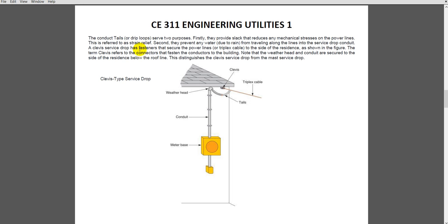As for the clevis, the drip loops serve two purposes. Firstly, they provide slack that reduces any mechanical stress on the power lines. This is referred to as strain relief. Second, they prevent any water due to rain from traveling along the lines into the service drop conduit. A clevis service drop has fasteners that secure the power lines or triplex cable. So our weatherhead is attached to the side of our houses. This is usually used in residential buildings. This distinguishes the clevis service drop from the mast service drop.